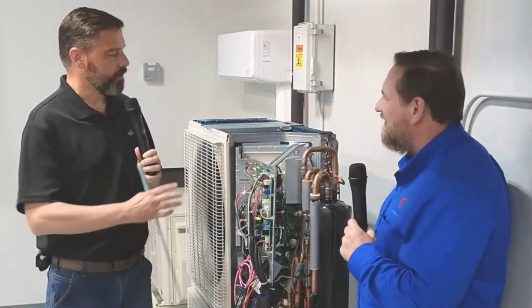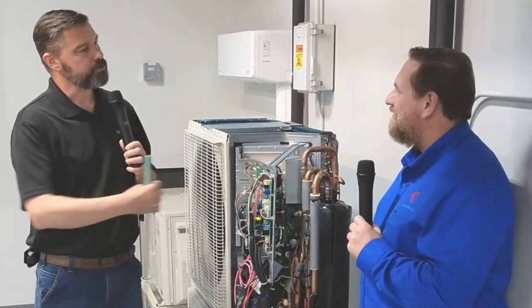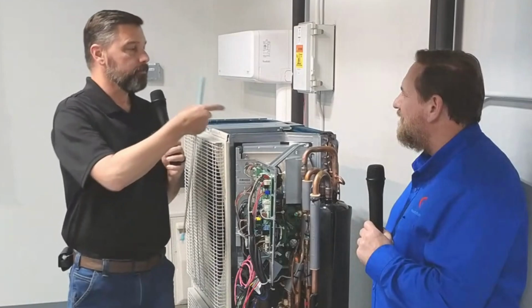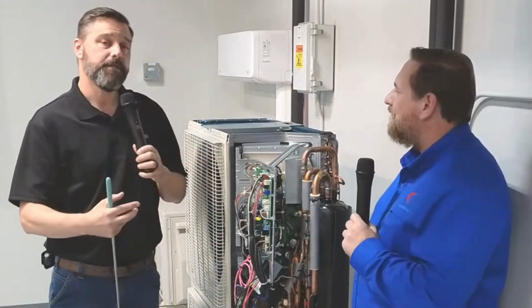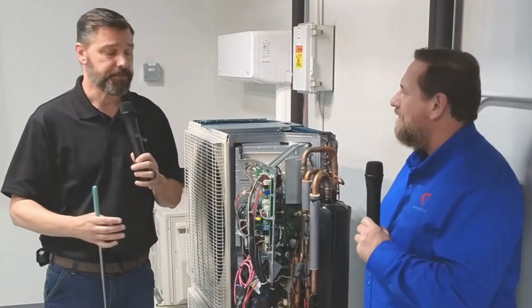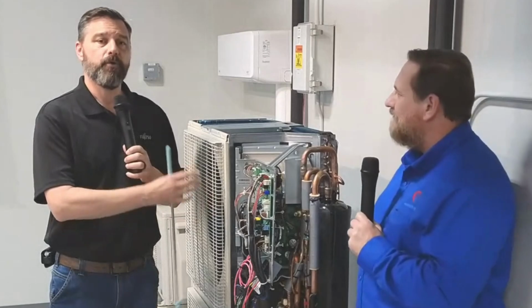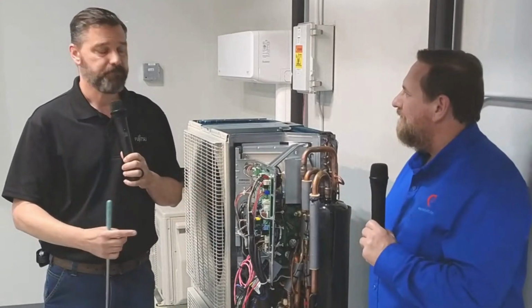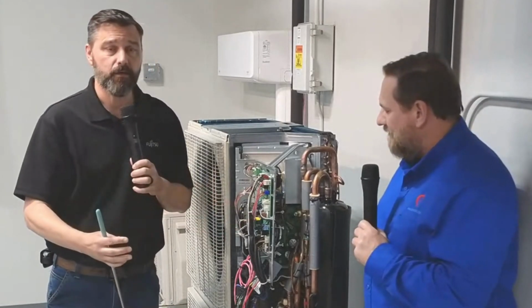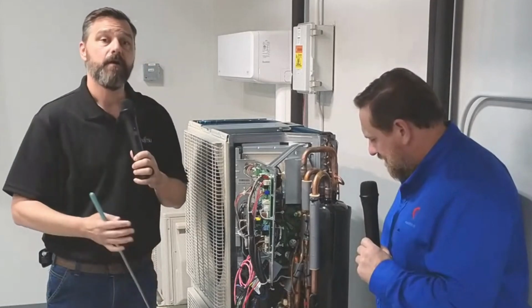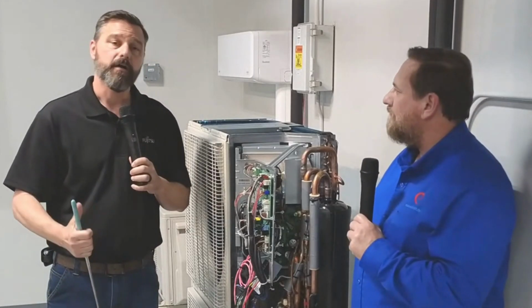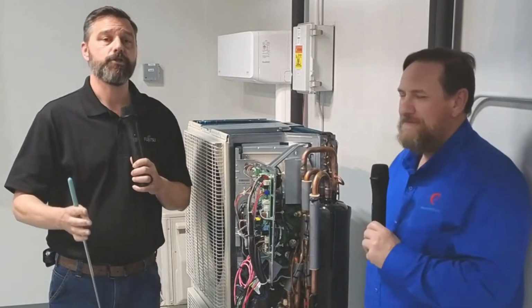Sure. So on our suitcase style or horizontal discharge fans, we have a blue phenolic coating. So when the system goes into defrost mode, it actually sheds water and ice. They've upgraded some of the programming on the board for low temperature heat. They've upgraded the wires to withstand that low temperature, and there's a base pan heater in there for low temperature operation. On our vertical discharge units, we have something called snow mode.